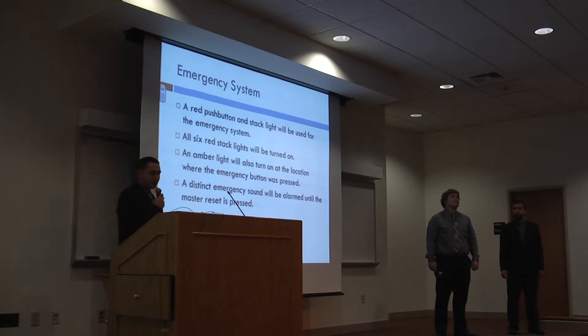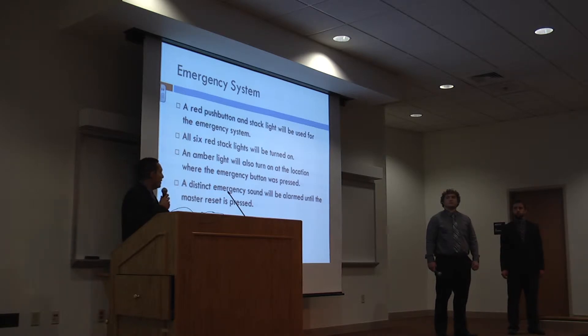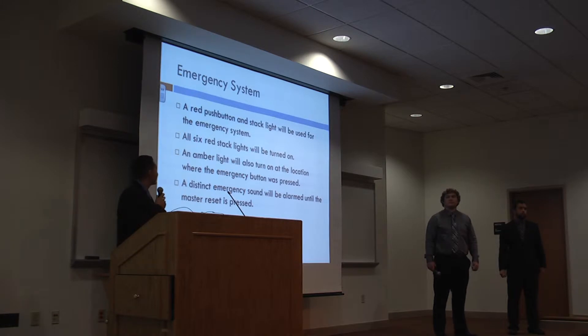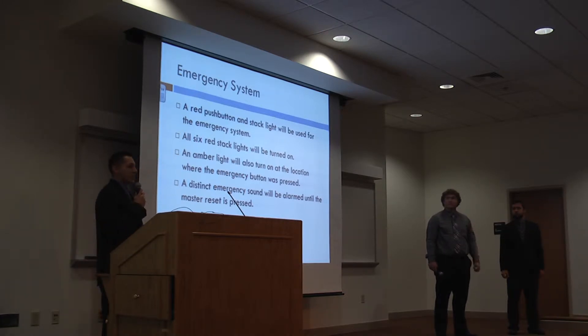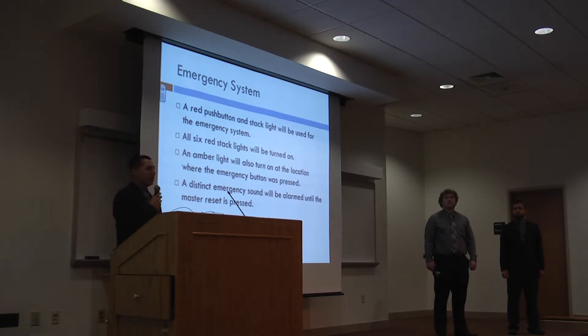For the emergency system, a red push button will be pressed at any of the six station locations. Whenever the red push button is pressed, a red light will come on. To help people identify where the emergency is coming from, we're also going to make the amber light come on wherever the red push button is pressed. A distinct emergency sound will come on whenever the emergency button is pressed. An example could be chemical spills — you can hit the red button so that people will evacuate.